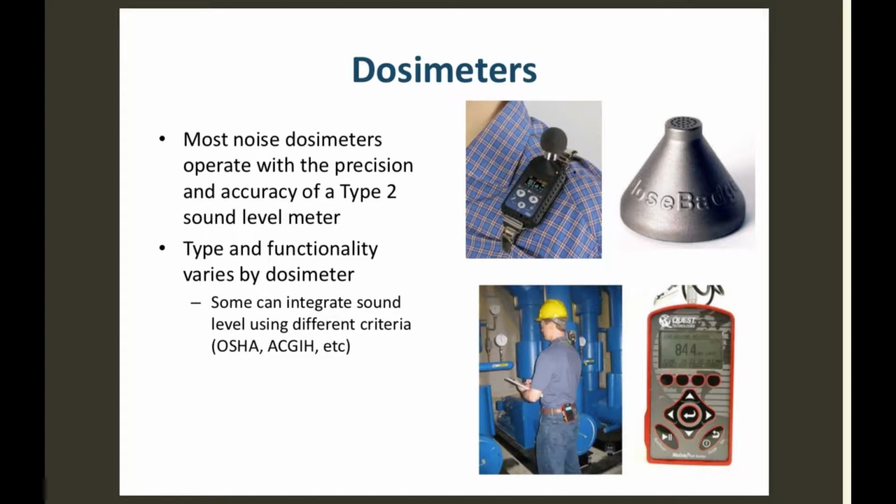You can't change the volume, because the volume is a standard. How often do you calibrate that? If you're doing field measurements or worker exposure, you want to calibrate it before and after you use it. Every time you use it, basically.